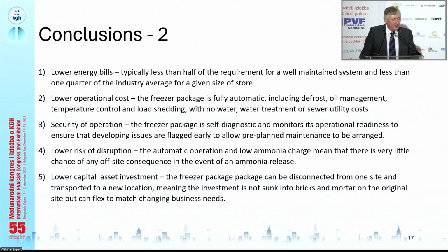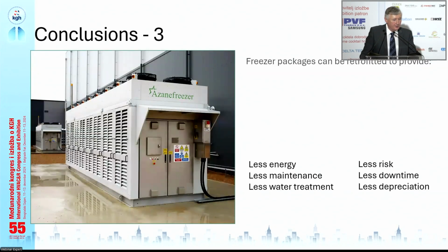And it could be less than a quarter of the industry average for that given size of store. It lowers the operational cost because the operation is now fully automatic, so there's less need for manual intervention. And it gives secure operation. You can trust that the plant will be operating. Lower risk of disruption because it's automatic, and there's very little chance of any off-site consequence in the event of an ammonia release. And the capital cost investment is spread over many years instead of all being one big hit to replace the central plant, which would be a much more expensive thing to do.